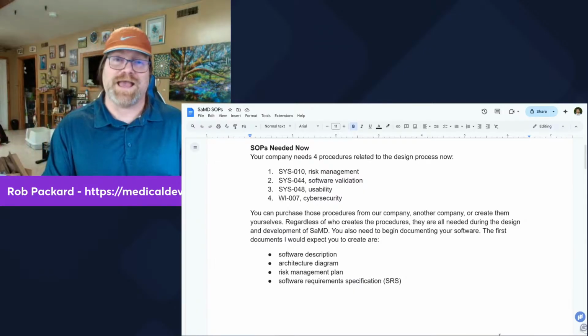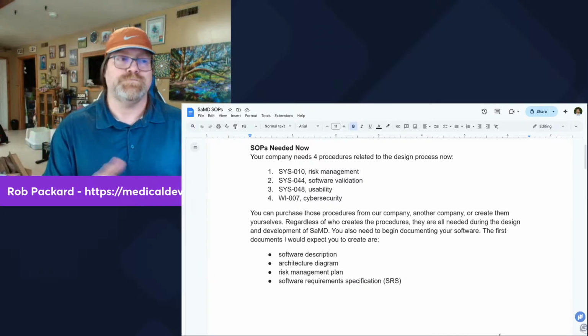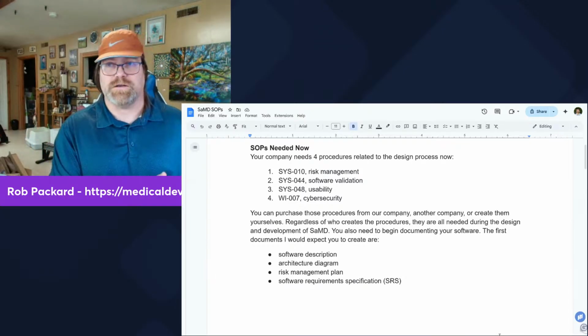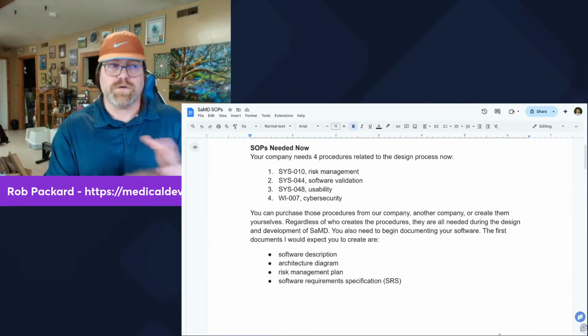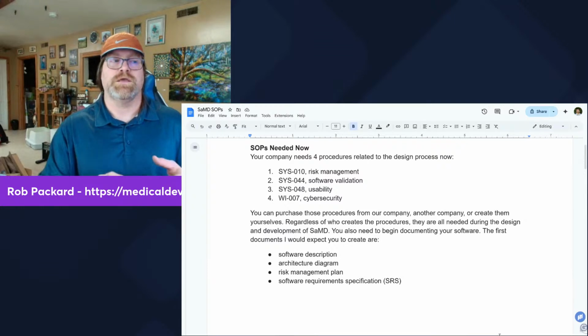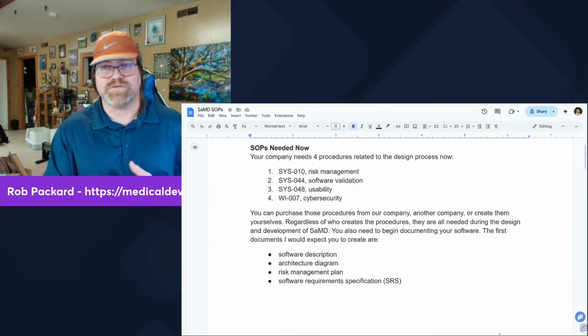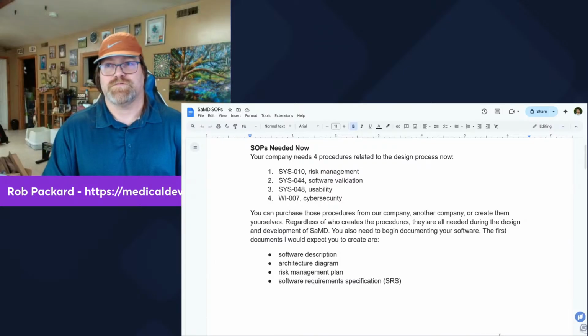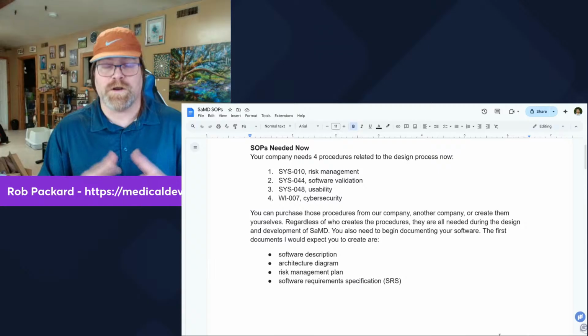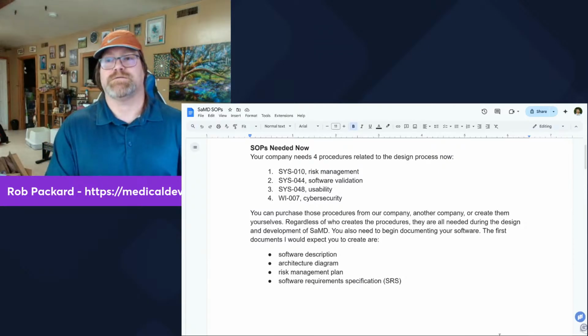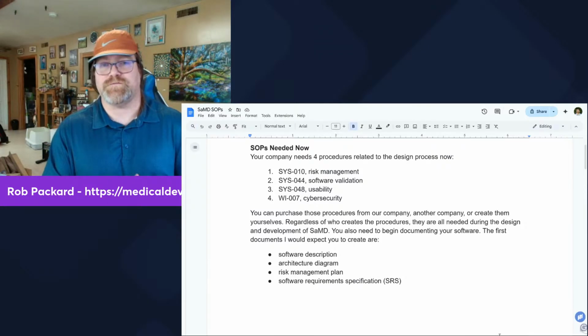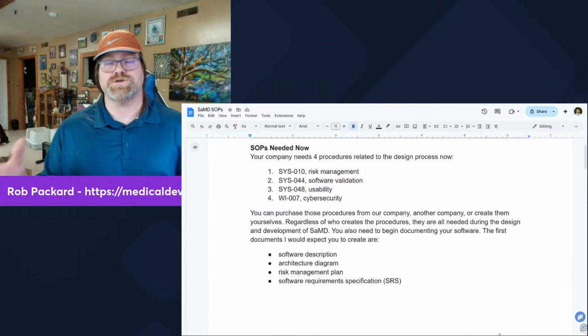It doesn't matter what it is. It has to have at least those 9. So that's what you need to start right at the beginning. So if you don't have a plan, you don't have a description, you don't have an architecture diagram, you don't have a draft SRS, you don't have these procedures, you haven't started really doing anything yet. You're playing. So stop playing and run a company correctly. You have to create a design history file. Start at the beginning. It's so much harder to retroactively create this documentation.